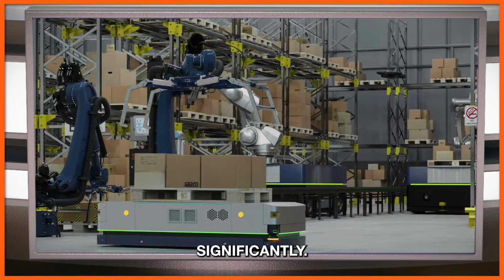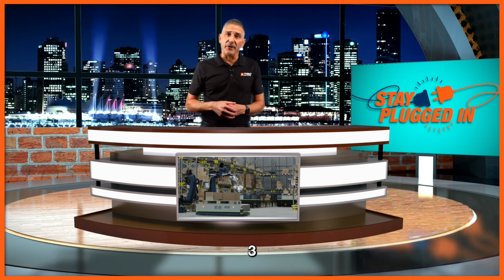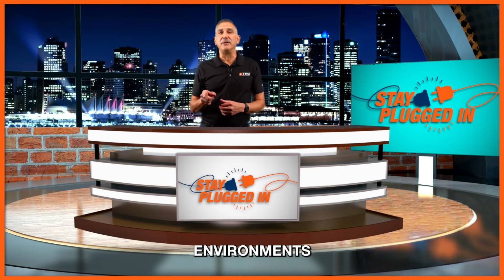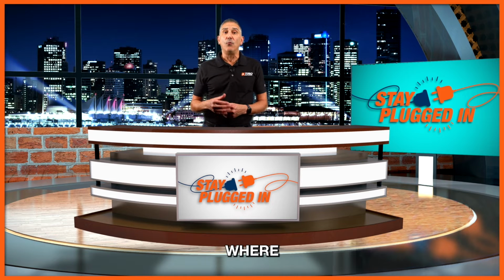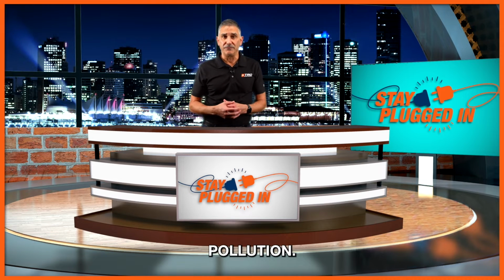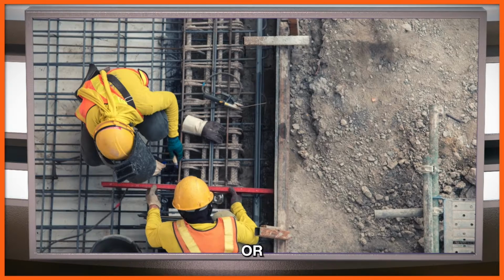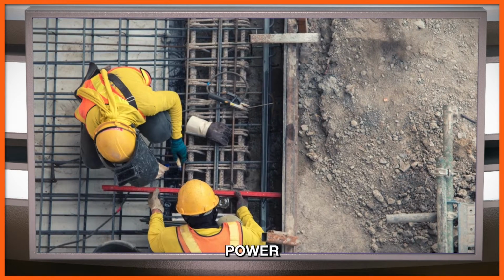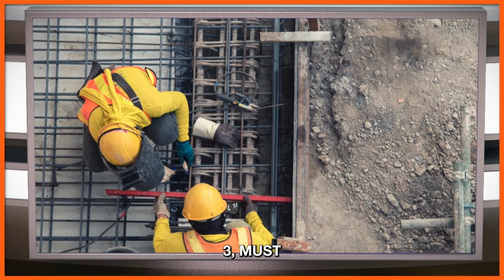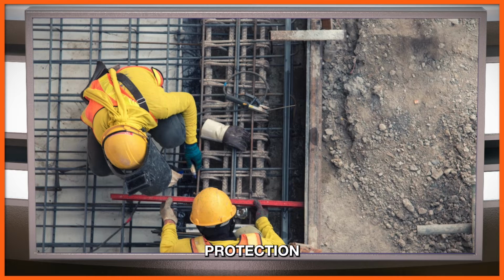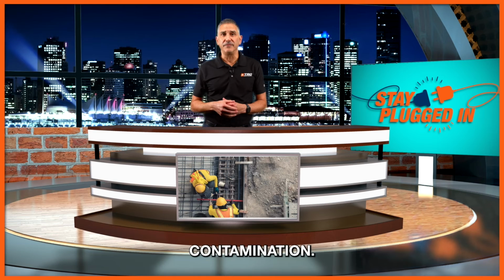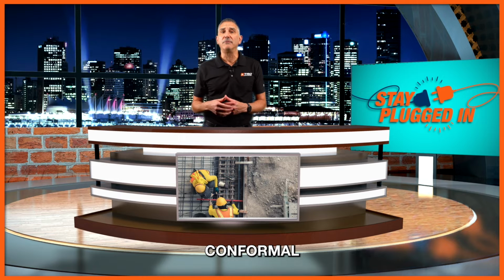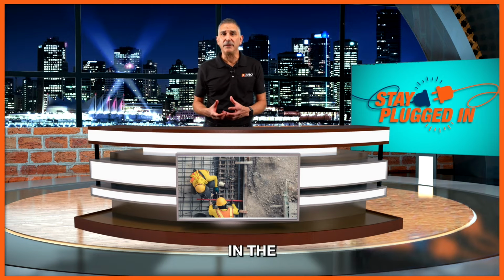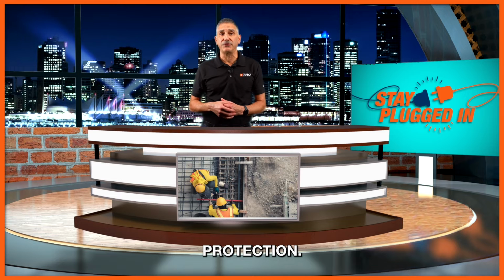But when we get to pollution degree 3, this level indicates environments that are significantly contaminated where there may also be conductive pollution. Examples of this would include industrial areas, construction sites, or locations with high levels of dust, moisture, or other conductive materials. Power supplies designed for pollution degree level 3 must have enhanced protection against such contamination. Examples of protection would include conformal coating of the electronics in the power supply or even ingress protection.